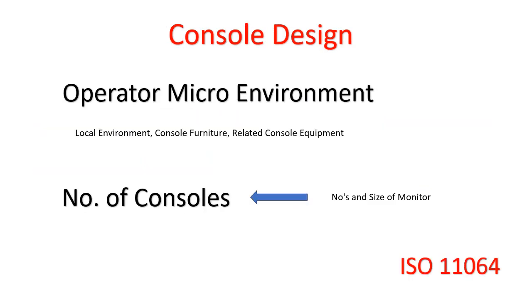With respect to console design, there are two major things: one is the operator micro environment and another is the number of consoles. Operator micro environment means the local environment, console furniture, and related console equipment. The number of consoles covers how many consoles are required, what the size of the monitor will be, and whether it will be double stack or single stack. ISA 101 also refers to another international standard, ISO 11064, within the console design section.